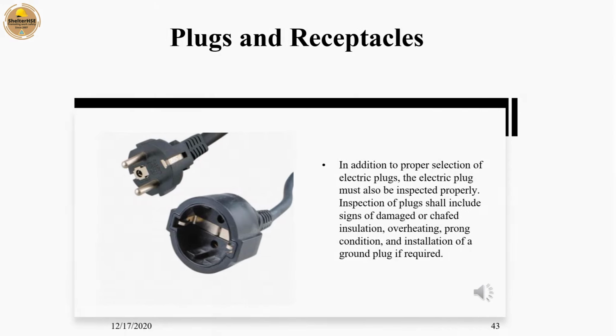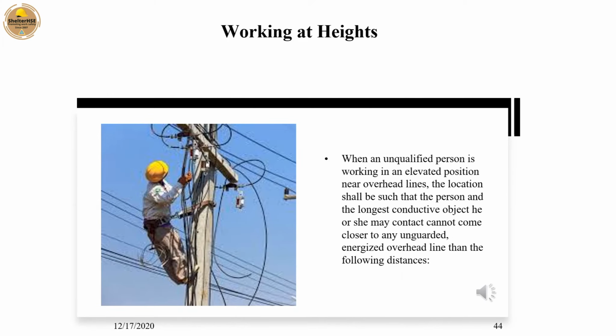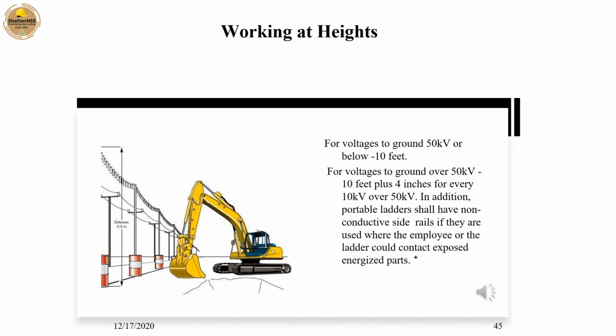When an unqualified person is working in an elevated position near overhead lines, the location shall be such that the person and the longest conductive object he or she may contact cannot come closer to any unguarded, energized overhead line than the following distances. For voltages to ground 50 kV or below, 10 feet. For voltages to ground over 50 kV, 10 feet plus 4 inches for every 10 kV over 50 kV. In addition, portable ladders shall have non-conductive side rails if they are used where the employee or the ladder could contact exposed energized parts.